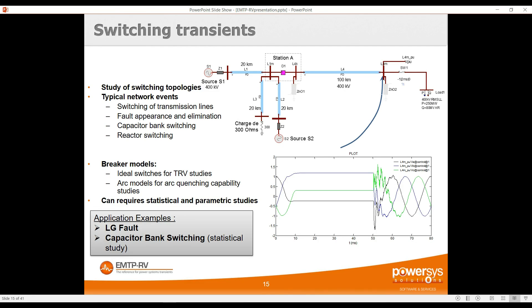Another type of switching study is line reclosing — very similar to the capacitor bank switching I demonstrated. At a certain point we disconnect a line due to an overload, leaving trapped charge on the line, and then close it again. Using the statistical capabilities, we can identify the worst overvoltage when closing the line with and without surge arrestors, and size the surge arrestor, the pre-insertion resistance, or even the point-of-wave switching.